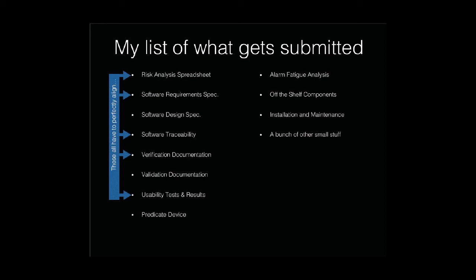I guess the other big one was when we chose all these default limits, because they recognize that if a device shows up, like a heart monitor in a hospital, it's going to get turned on with whatever the default settings are. Most people don't change them. So they wanted to know how we came to the conclusion that our default limits were valid. So we had to go poll a bunch of doctors and provide all the references we used for those default limits. So default limits need a validation and a rationale, and so does the usability testing.